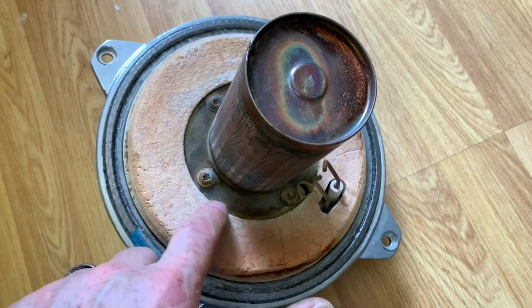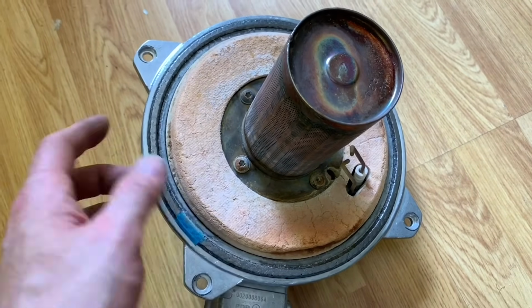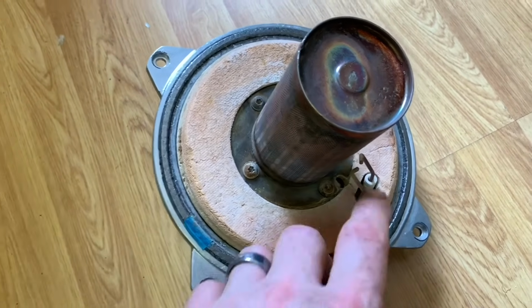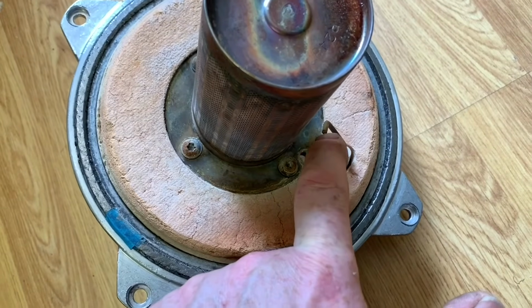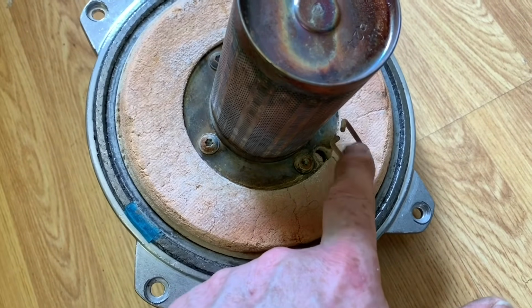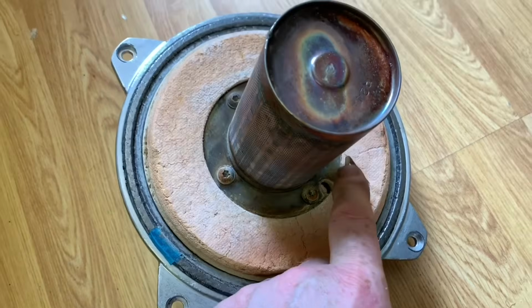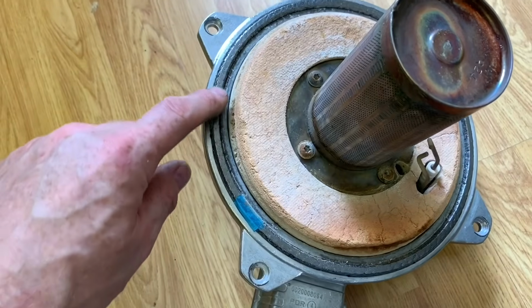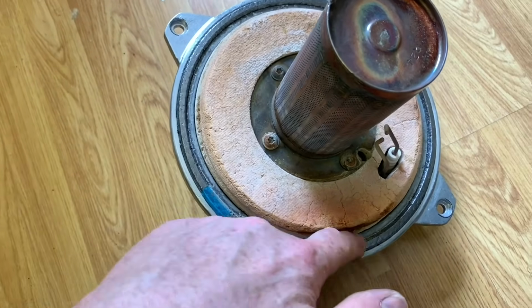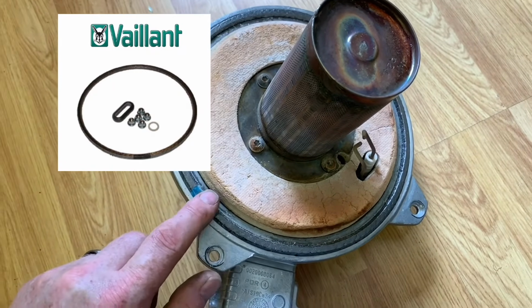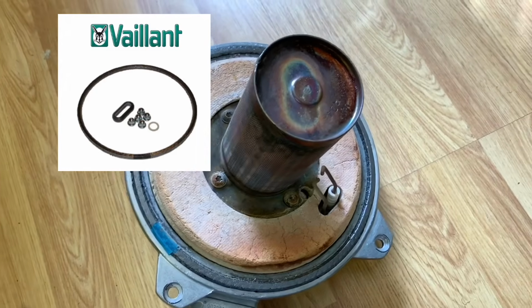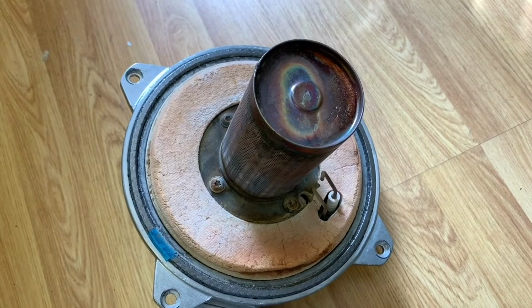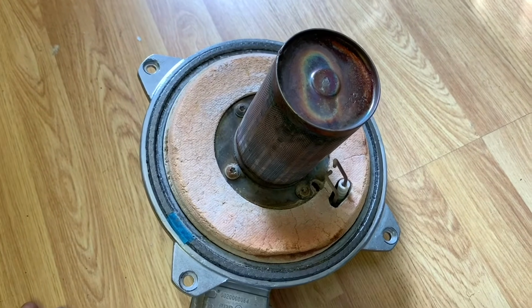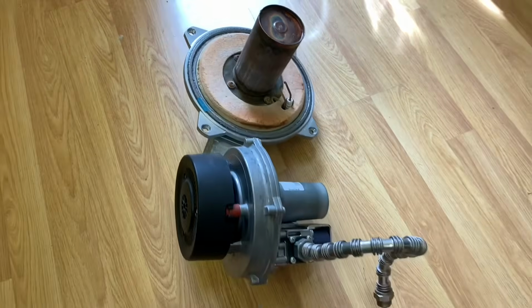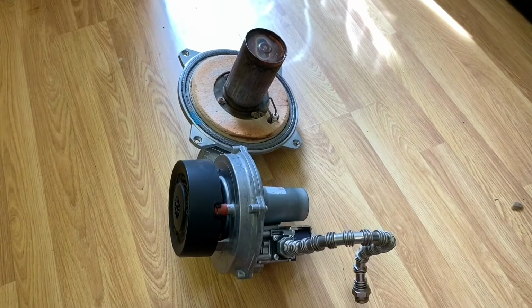This is insulation, okay, to stop the front door getting hot. And this is our spark electrode. So our flame rectification, flame conductance electrode. Now this is the gasket, what needs to be replaced every time we take this burner door off. You can see there's actually a joint in it. So every time you open it up, you'll need one of these gaskets. Cost about 20 quid. So that is our full heat engine.